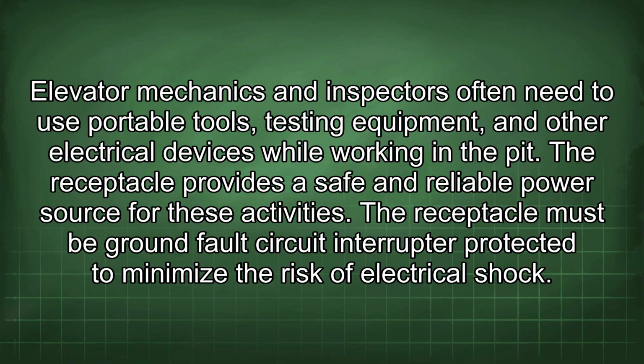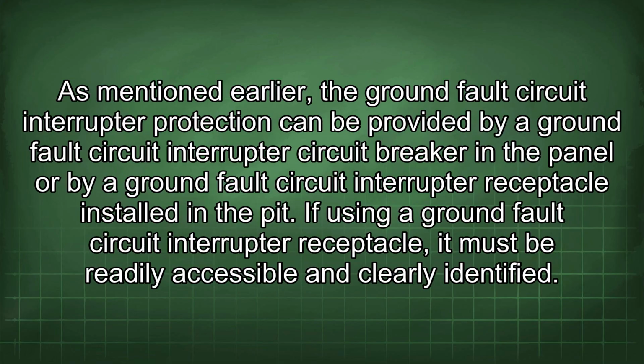Elevator mechanics and inspectors often need to use portable tools, testing equipment, and other electrical devices while working in the pit. The receptacle provides a safe and reliable power source for these activities. The receptacle must be ground fault circuit interrupter protected to minimize the risk of electrical shock. As mentioned earlier, the ground fault circuit interrupter protection can be provided by a ground fault circuit interrupter circuit breaker in the panel or by a ground fault circuit interrupter receptacle installed in the pit. If using a ground fault circuit interrupter receptacle, it must be readily accessible and clearly identified.